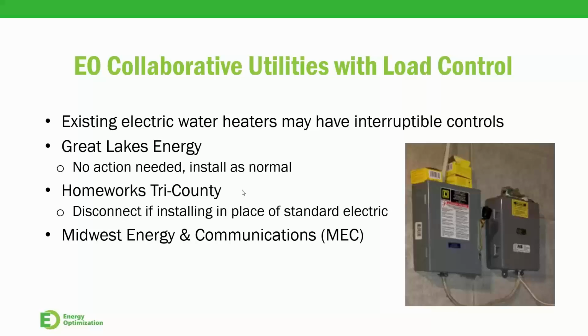However, if you do see this for Homeworks Tri-County and Midwest Energy and Communications, we prefer you not to connect a heat pump water heater to the load control, just because we don't want to worry about damaging any sensitive electronic components or the compressor in these new heat pump water heaters.